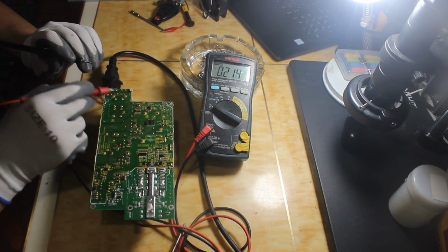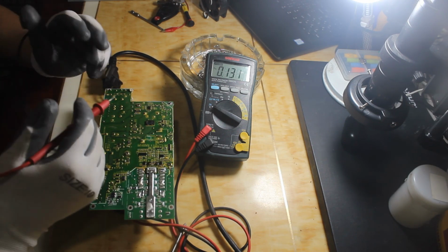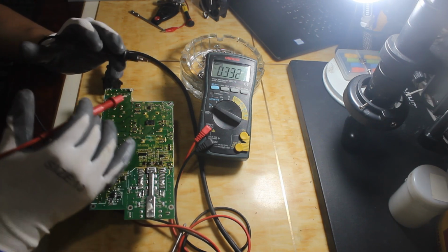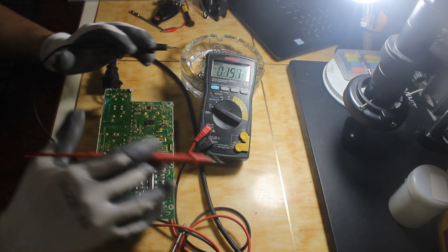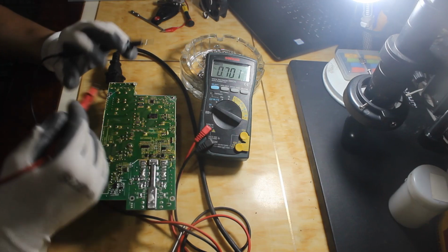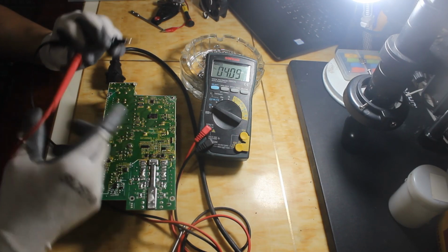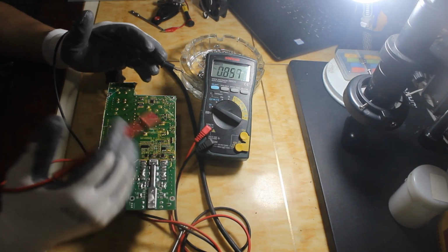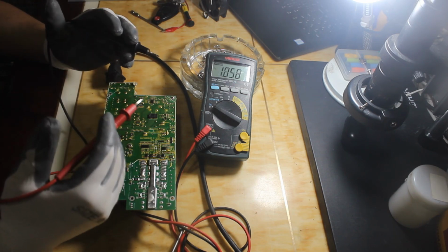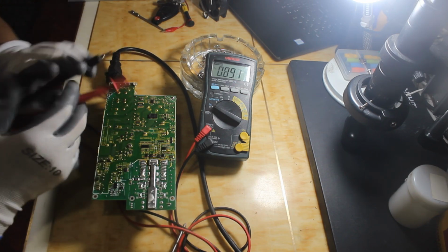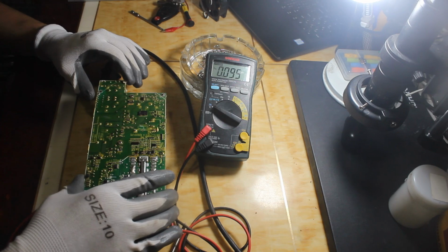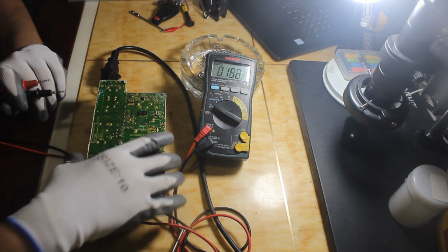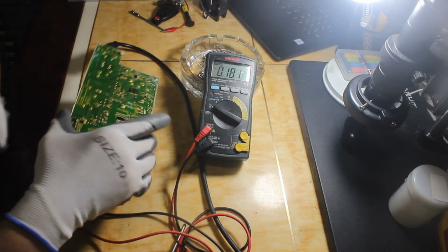After we test the AC power line, we need to measure whether the positive and negative poles of the output terminal are short circuited or not. If there is no short circuit, we measure whether there is voltage input in the front section. So we talk about this side.